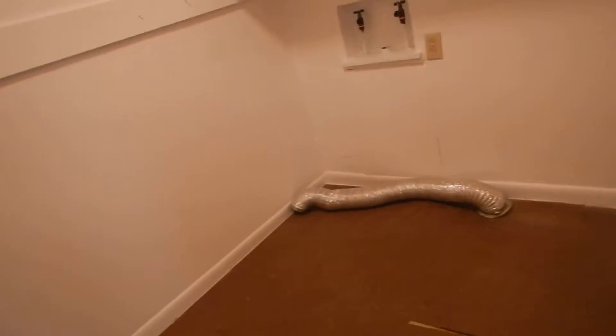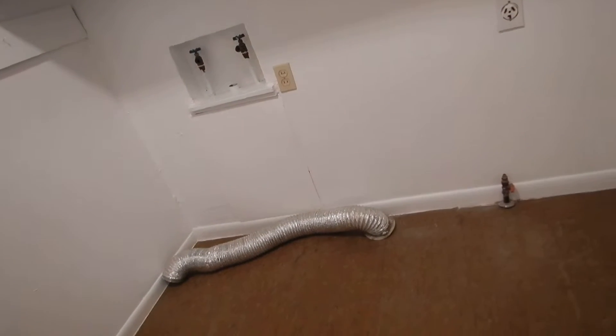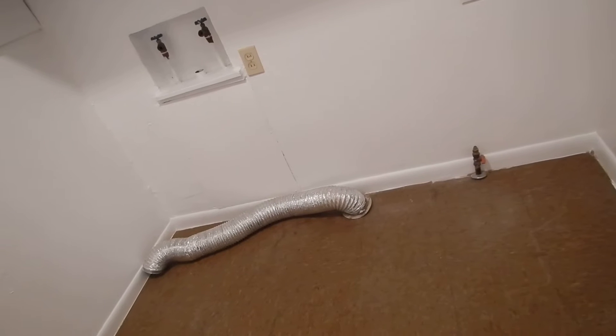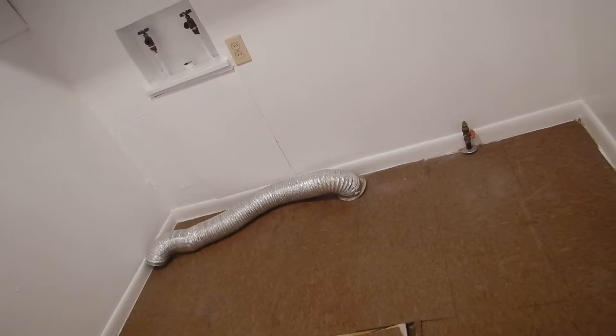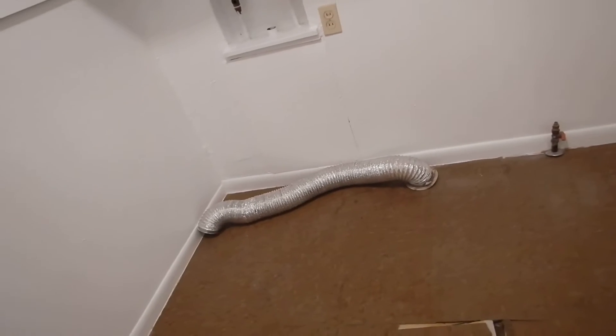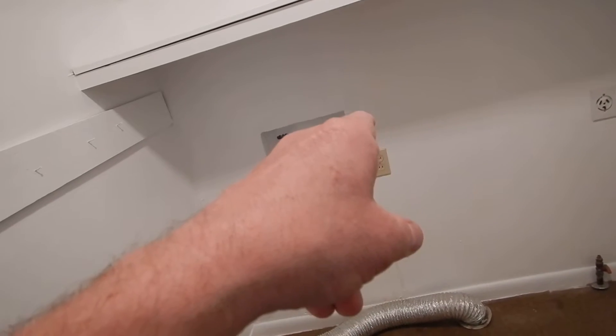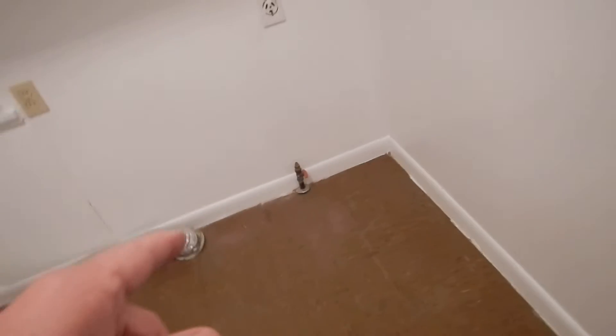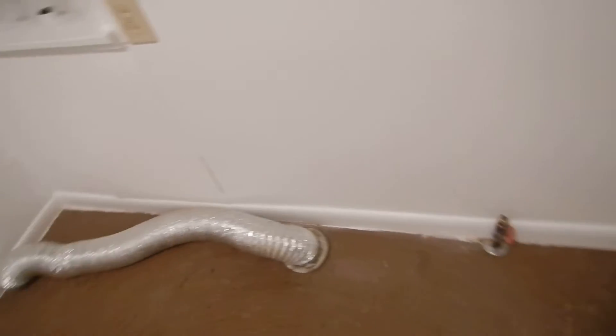Moving on to the laundry. I haven't been in the crawl space yet — I'm going to try to get in there. This vent is not labeled; the length of it should be labeled, and it does not have a hood outside. The laundry does not have grounding nor GFCI. If you've got a gas dryer, you're good to go, but if you don't have a gas dryer, that valve should have been capped off.